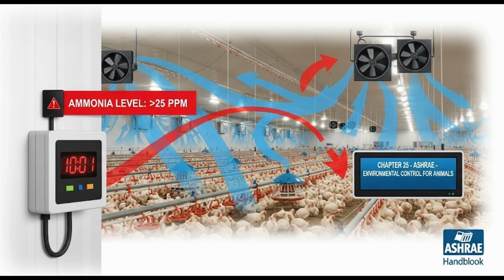60 air changes an hour? That's a lot of air moving. So how do they calculate the actual heating or cooling needed? You mentioned heat balance. Yeah, it's called a sensible heat balance. Basically, accounting for all the dry heat, you add up the gains: body heat from the animals, heat from lights, equipment, maybe warm air coming in, and subtract the losses, like heat going out through walls or roof, or lost when you ventilate with cold air.